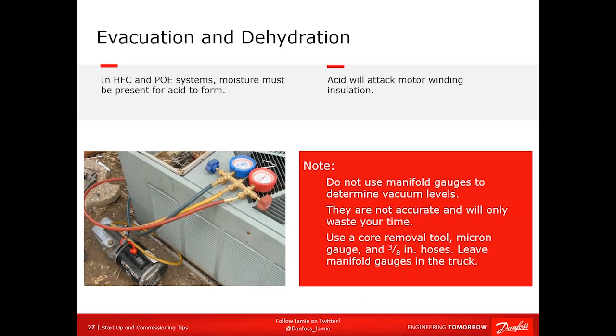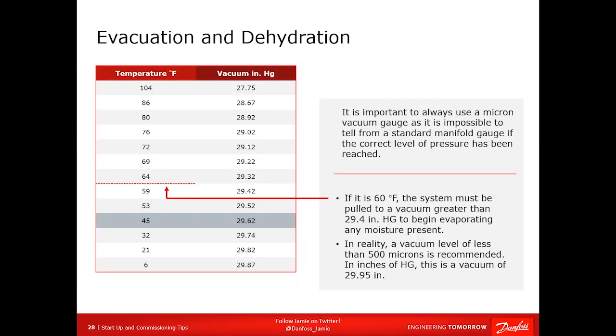So as I said before, in HFC POE systems, you need moisture in order to have acid. Acid will attack the windings. So a couple of recommendations. Toss out the manifold gauges, all right? It's not the 1970s anymore. All right, we have micron gauges, we have core removal tools, we have 3/8 and 1/2 inch vacuum rated hoses. You can literally cut down your evacuation time in half, all right? At the same time, you're going to have an accurate representation of what is going on in the system.